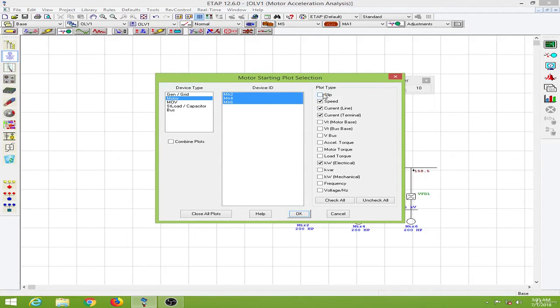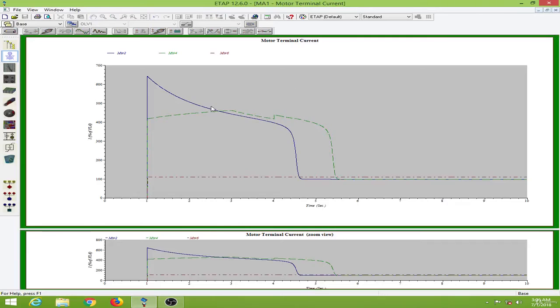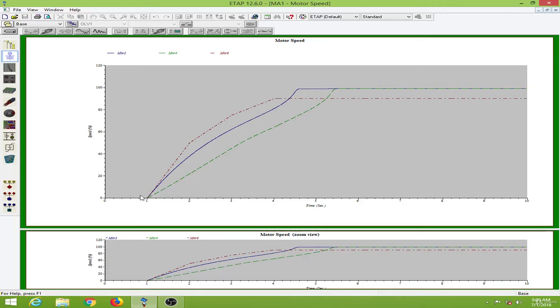I will choose these three options and also observe the slip as well, then click OK. We now have the motor terminal currents for the three motors. Motor 2, which does not have a starter, has more than 600 percent of full load current during the inrush period. Motor 4 with the auto transformer starter has about 400 percent of full load current during inrush. Motor 6 with the V/f drive has only the full load current during the starting period.